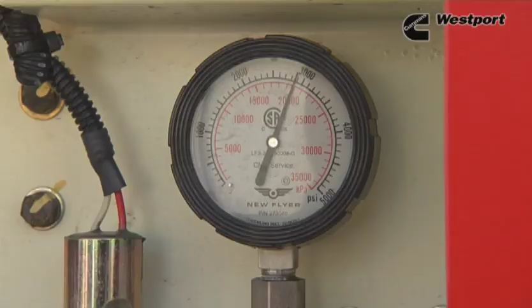Time or slow fill stations are typically used when vehicles are parked between shifts and can take several hours to refuel. But time fill stations are less costly to build and operate and are often the choice for fleets that are not active overnight. At this facility, we have what's called a time fill CNG fueling station. Basically, you take gas out of the pipeline, compress it to 3,600 psi, and fuel the entire fleet simultaneously through a cascade filling system.